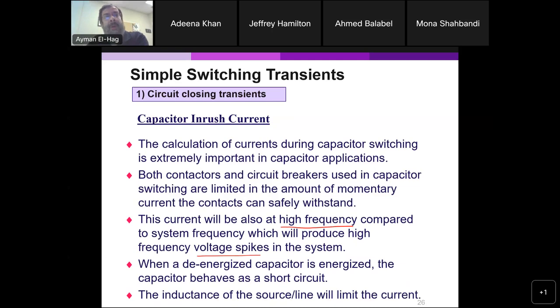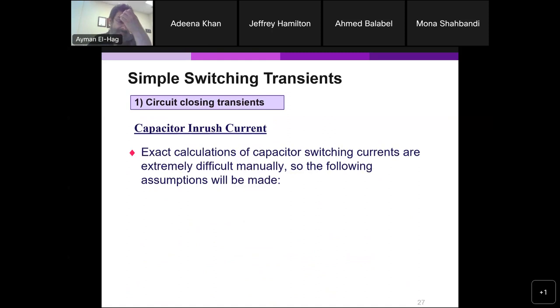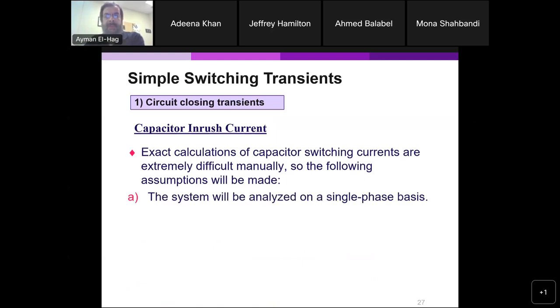Now, the inductance in the system is the only thing that will limit the current, because at the moment of switching the capacitor was not charged, so it acts as a short circuit. What limits the current through the capacitor is basically the inductance of the source and the inductance of the line. As I just hinted, exact calculations of these currents are very difficult. Usually we use software to do that, like EMTP or EMTDC. These programs are used to simulate transients in the power system. If you have a realistic or big system, it is very hard to find how much surge current there is. But to do it manually, you have to make certain approximations. You have to do it in a single phase.